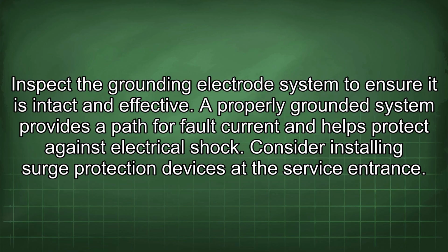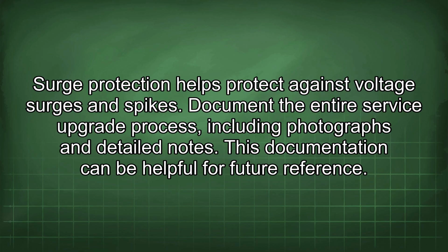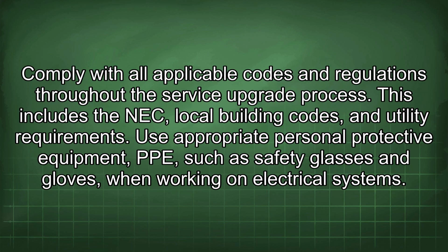Inspect the grounding electrode system to ensure it is intact and effective. A properly grounded system provides a path for fault current and helps protect against electrical shock. Consider installing surge protection devices at the service entrance. Surge protection helps protect against voltage surges and spikes. Document the entire service upgrade process, including photographs and detailed notes. This documentation can be helpful for future reference. Comply with all applicable codes and regulations throughout the service upgrade process. This includes the NEC, local building codes, and utility requirements.